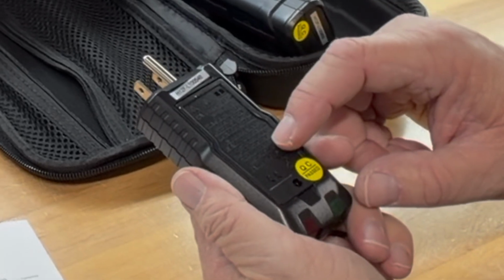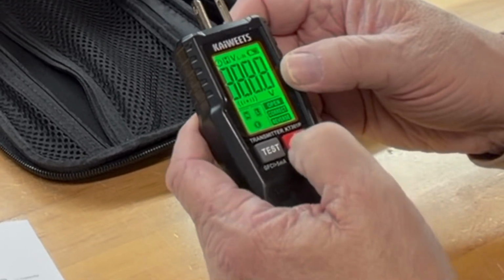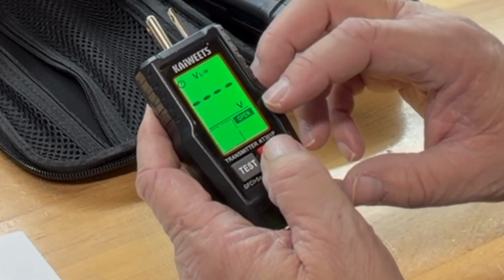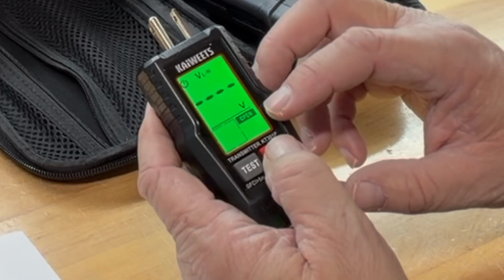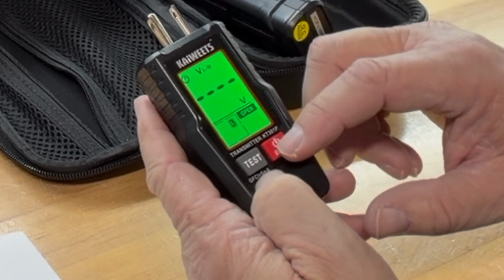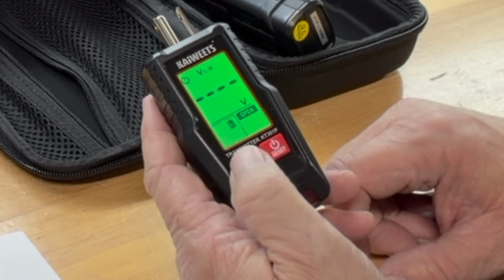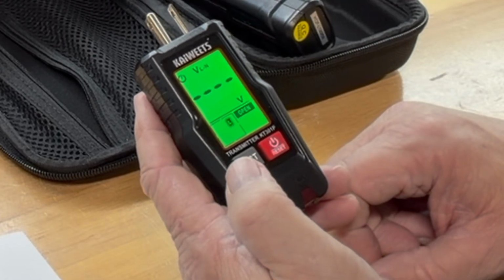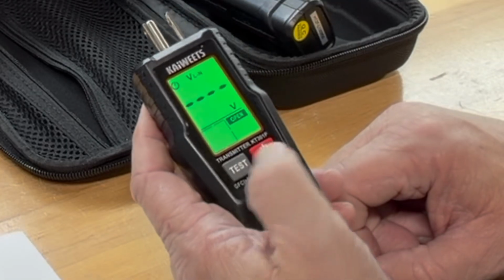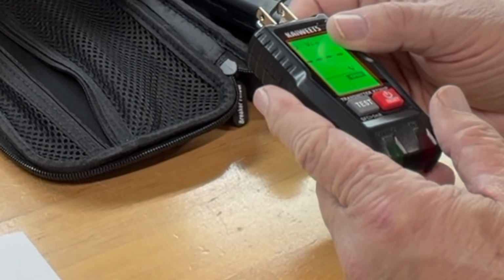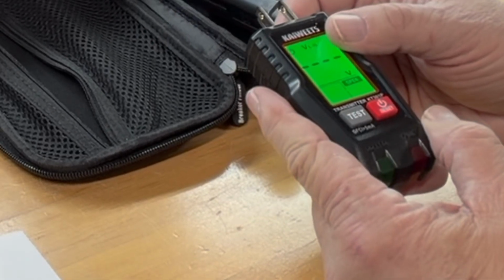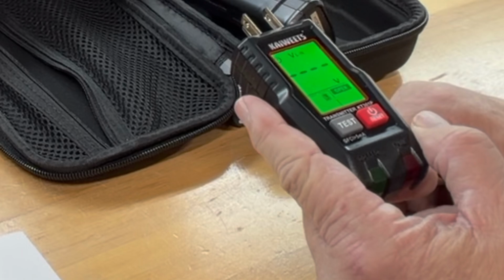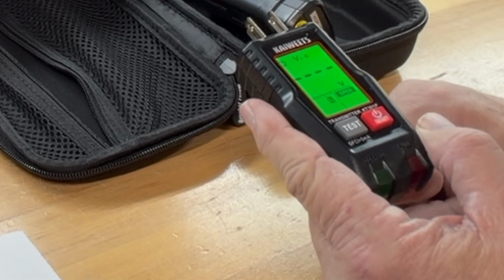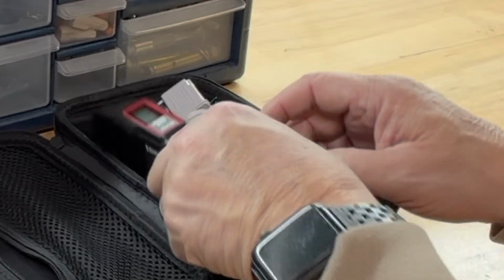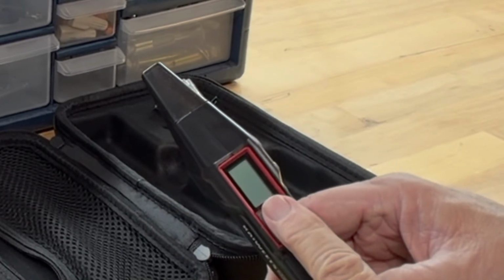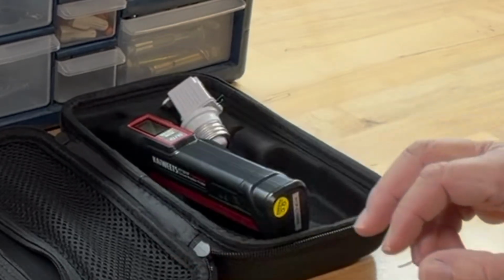Now that we have the batteries in the transmitter itself, we'll turn it on. You can see the LCD screen. It'll tell you what volts, and if it's an open or closed circuit. And this button here on the left is the test button for testing ground fault circuit interrupter plugs. So you would plug this into the outlet that has a ground fault protection, press this test button, and it should kick off the ground fault circuit to indicate that it is working properly. Between each test, you want to hit the reset button to clear out any previous testing.